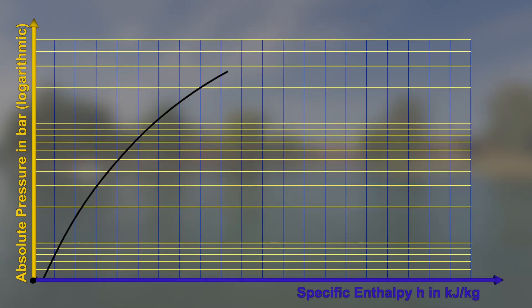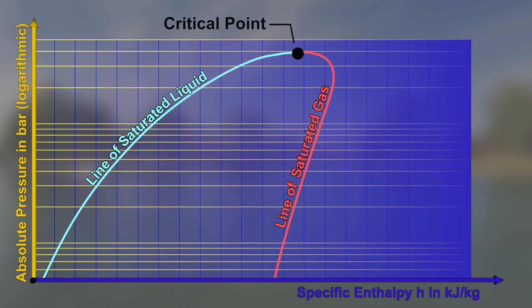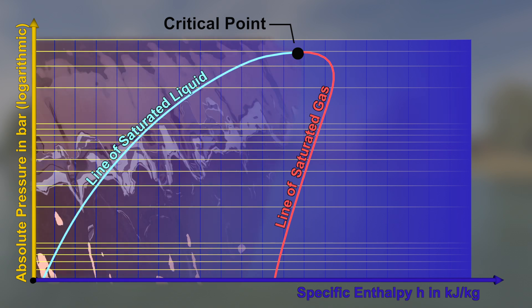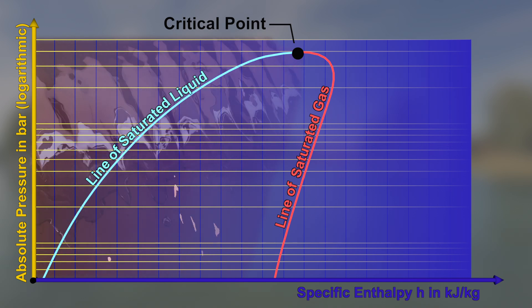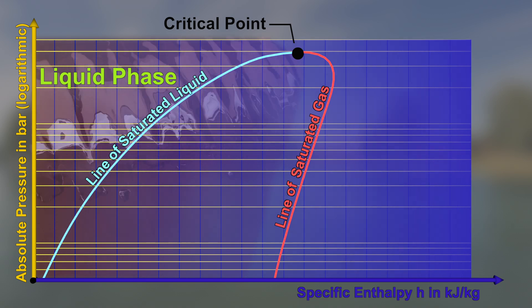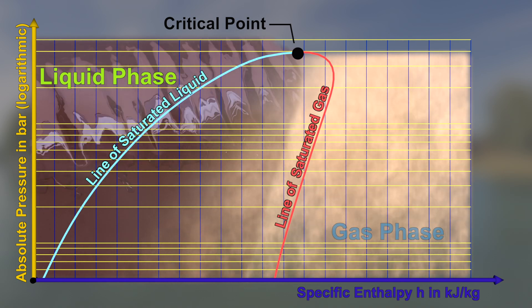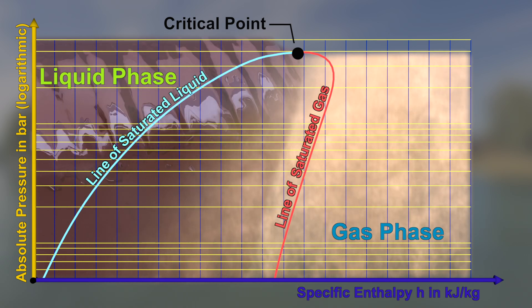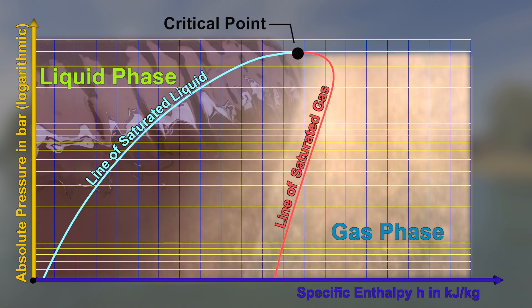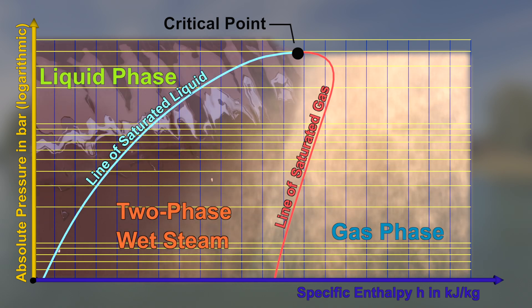A pressure enthalpy diagram contains a dome-shaped area. It stretches from the line of saturated liquid on the left to the line of saturated gas on the right. Both saturation lines meet at the top in a critical point. To the left of the saturated liquid line, the fluid is in a liquid state and the specific enthalpy h is low — this is the area of the liquid phase. To the right of the saturated gas line, the fluid is in a gaseous state and the specific enthalpy h is high — this is the area of the gas phase. In the dome-shaped area between both lines, both the liquid and gaseous phases exist simultaneously, and it is called the two-phase domain or wet steam domain.